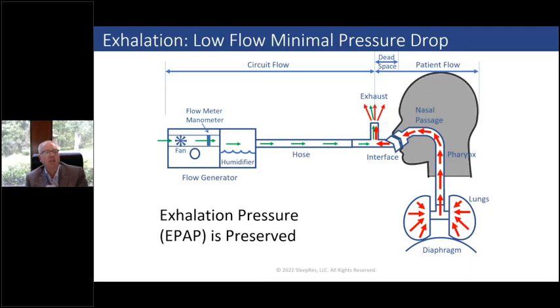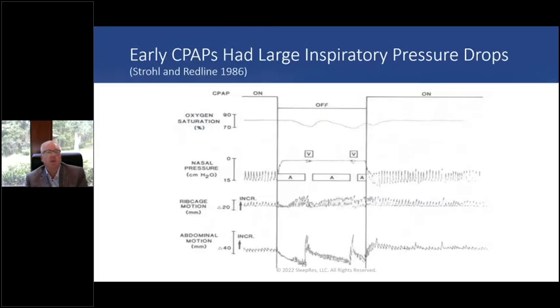That's the inspiratory pressure. On exhalation, now you have low flow, because there's no patient flow—they're actually breathing out, and most of the exhaust flow is probably coming from the patient. So there's very little flow coming from the blower, very little circuit flow, and little pressure drop. So EPAP is usually preserved.